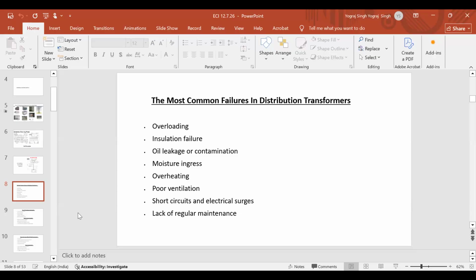Now, overheating: there is a gauge given outside. Nowadays, all this data is going into a digital system called SCADA or BMS, Building Management System, where it is reflected what the load is and what the temperature is. So all those things are to be monitored. Otherwise, in the physical system, people will not go to different places and take the reading. Ventilation: wherever the transformer is kept, if it is outside, ventilation is not an issue, but for an indoor substation ventilation is a big issue. Short circuits and electrical surges happen if your protective system is not working properly. It may lead to transformer failure also. Lack of regular maintenance needs no explanation.